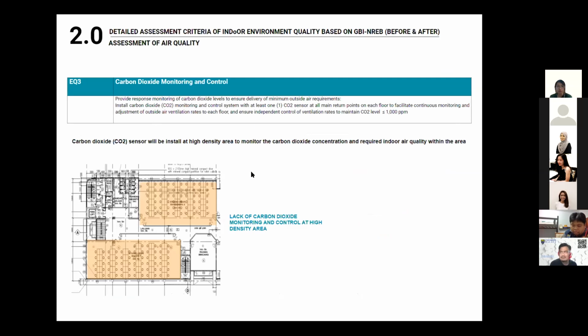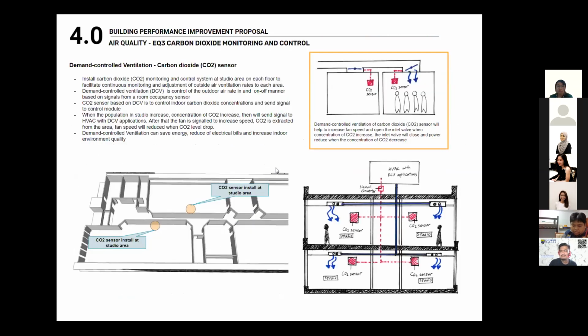For EQ3, because the whole building lacks carbon dioxide monitoring and control, we propose to have demand control ventilation, which monitors CO2 at high density areas, which is the studio area and the Bilik Kuliah area. We will install a CO2 sensor at the studio area, and when the population in the studio increases, the concentration of CO2 also increases. So we send a signal to the HVAC with the DCV control application, so the fan will speed up and extract the CO2 to outside, and the fan speed will reduce when the CO2 level drops.